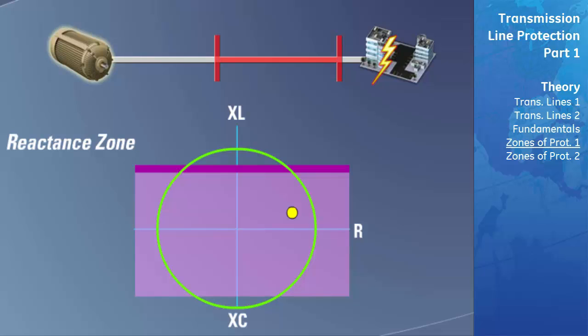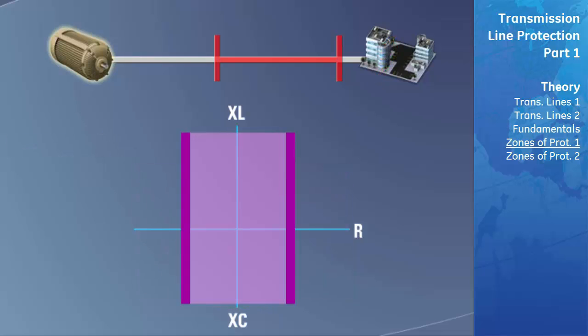The next zone of protection we will look at is a resistance zone. This type of zone is used to detect when the impedance of the fault has a very high inductive component in it. If the fault does have a high inductive impedance, this indicates that there is very little or no resistive load at the end of the transmission line and it is likely that the fault is located on the transmission line. This type of zone is usually never used to trip a transmission line on its own but is normally used to supervise another distance zone of protection.